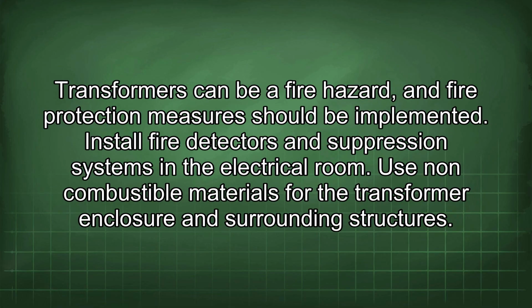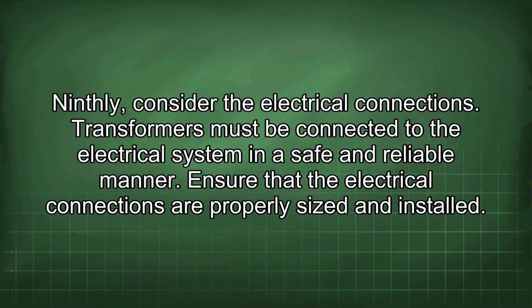Transformers can be a fire hazard, and fire protection measures should be implemented. Install fire detectors and suppression systems in the electrical room. Use non-combustible materials for the transformer enclosure and surrounding structures. Ninthly, consider the electrical connections.